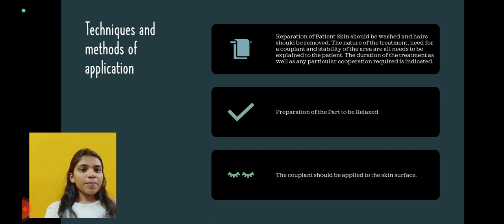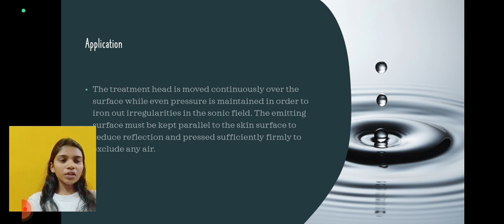The emitting surface must be kept parallel to the skin surface to reduce reflection and pressed sufficiently firmly to exclude any air. We have to make contact and stay in contact with the skin and the ultrasound head. We must not allow air to pass between the skin and the ultrasound head.